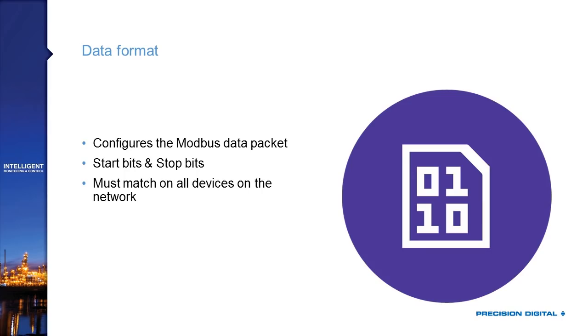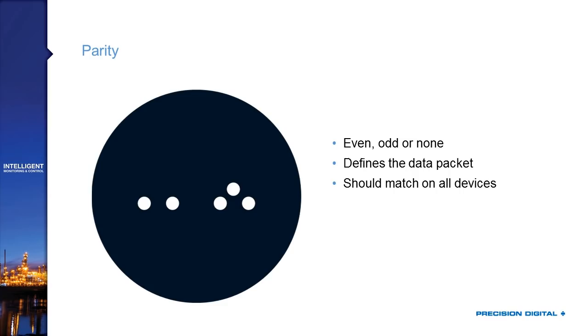Parity is another item that must match across everything on the network. Parity is set to even, odd, or none, and it defines error checking in the Modbus signal. Essentially, parity counts all the ones in the transmitted Modbus word and sends that count to the other device, which checks it against its own count. For example, with a four-bit word of 1-0-1-0, you have two ones — an even number — so a parity bit indicating 'even' is appended. If a transmission error flips a bit, the count won't match, revealing the error.